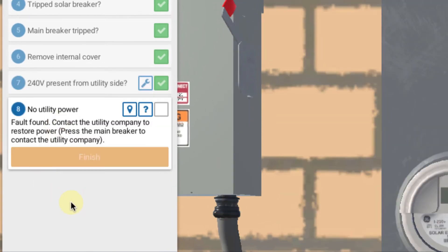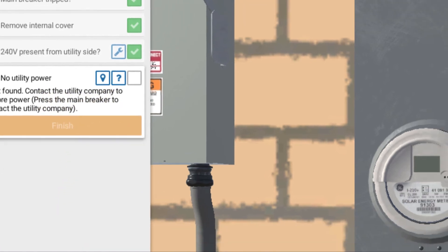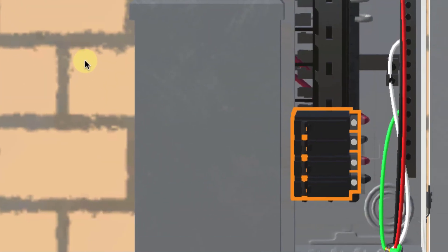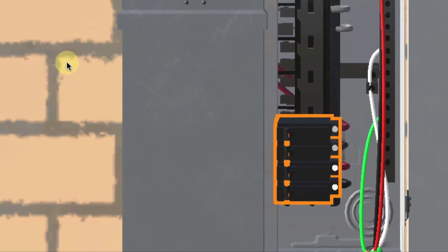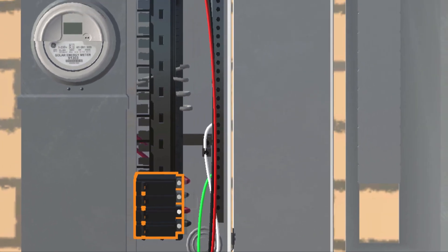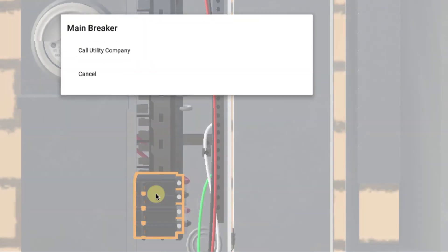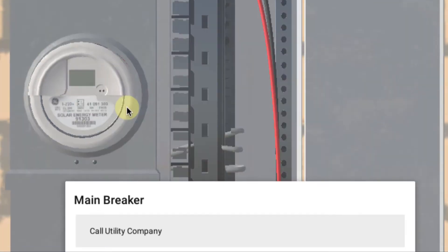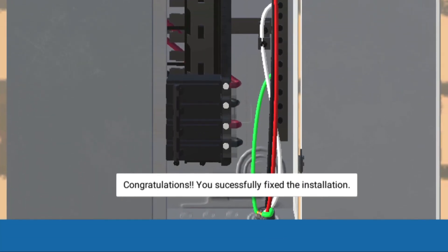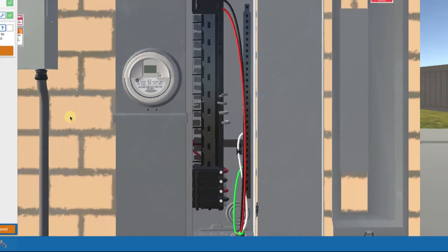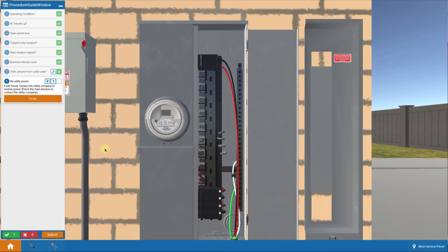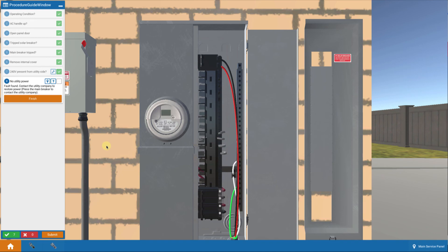Okay, fault found. You have to contact the utility company to restore power. What's going on here is that you may not have any problem at all with your solar system, but there's some problem with the utility system. So we're told to touch on the breaker, and it brings up a call to action that says call the utility company. When I do that, it says congratulations, you've fixed the installation. At least you've taken the proper action to get the utility involved in restoring your power. So this is a curious type of fault where you don't have to chase down your tail on your system. There's something wrong on the utility side.